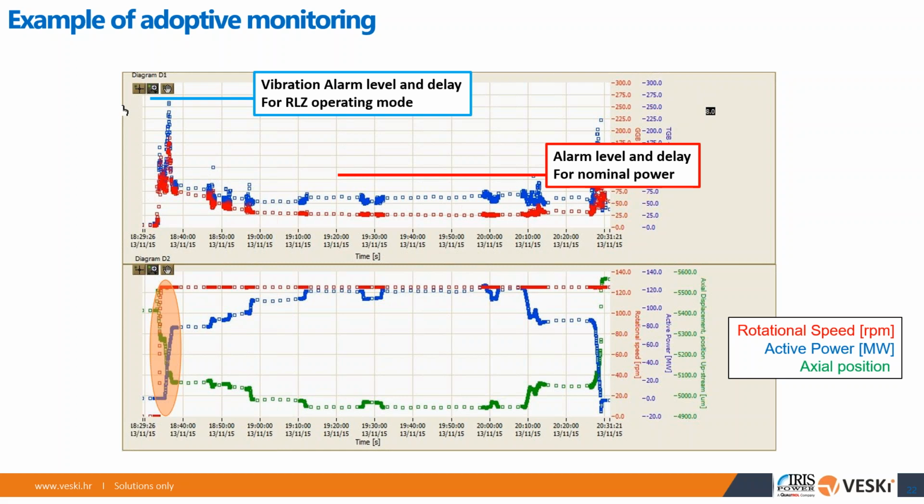So this is our theory. It's not confirmed. This is not just ours, but we discussed it with some people that have the same opinion. So basically, the energy has nowhere to go. It cannot be transferred to the turbine properly. And then whenever you have more energy than the system can absorb, it releases itself in self-exciting vibration.